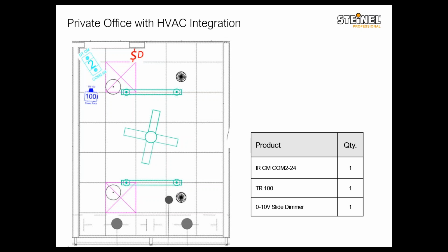And you would need a power pack for the lighting. You can use a slide dimmer if the fixtures are dimmable. And then the second, the HVAC relay would be connected to the HVAC system. If you have a VAV, to the VAV, or if you have a building management system, that can go back to the building management system, and you can do it remotely.